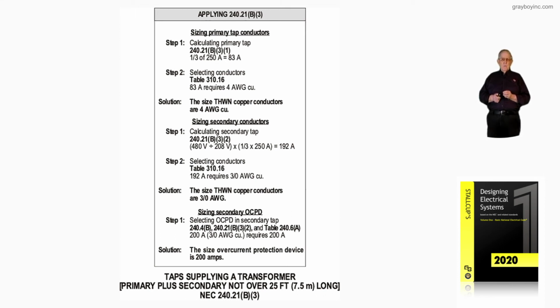Selecting the secondary overcurrent device now in accordance with 240.4(B), 240.21(B)(3) item 2, and the selection of the overcurrent device from Table 240.6(A), a 3/0 conductor worth 200 amps to us ampacity-wise requires a 200 amp overcurrent device. The 200 amp overcurrent device protects the wire and protects the panel board where the 200 amp overcurrent device is installed.